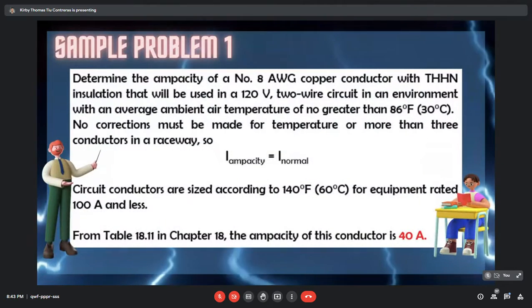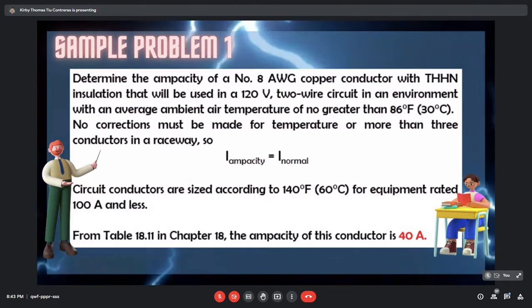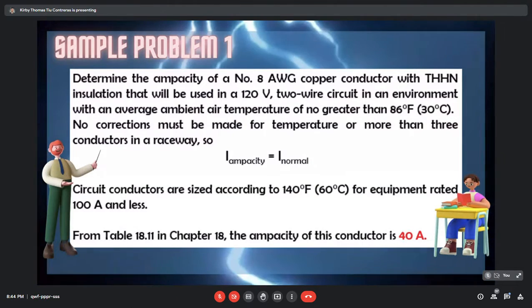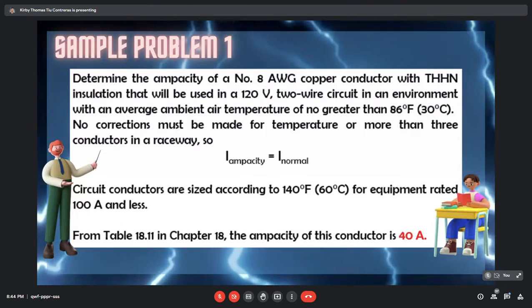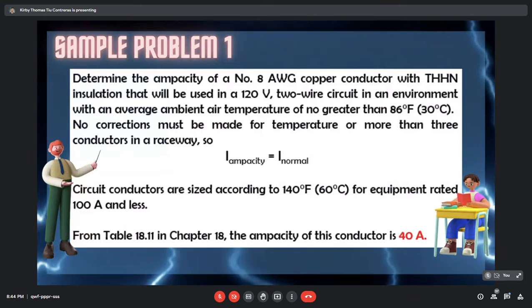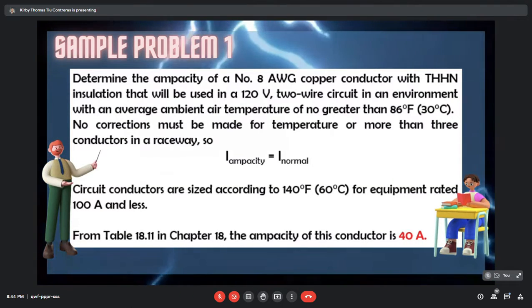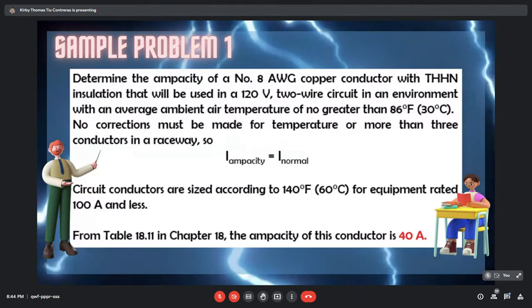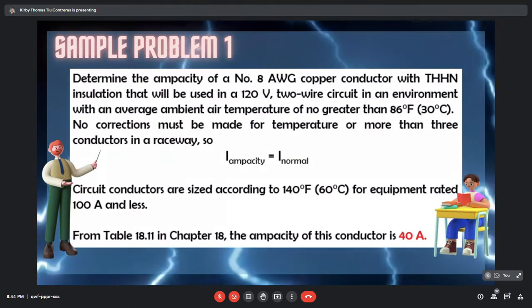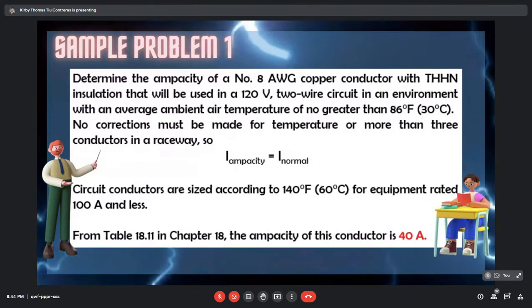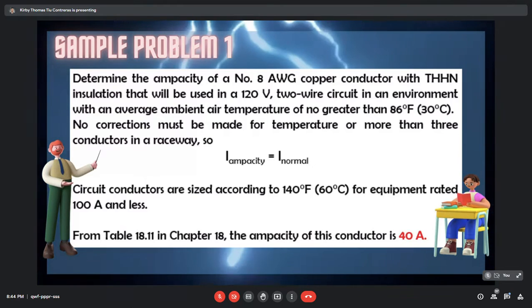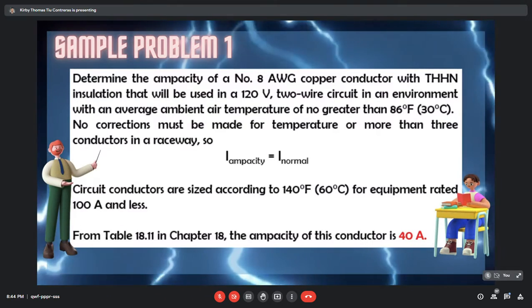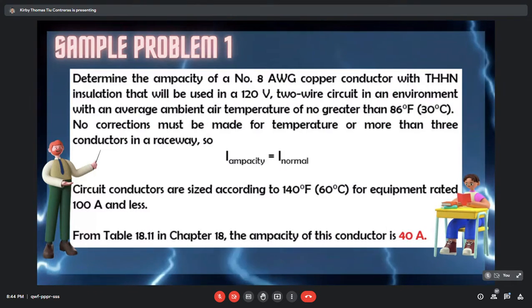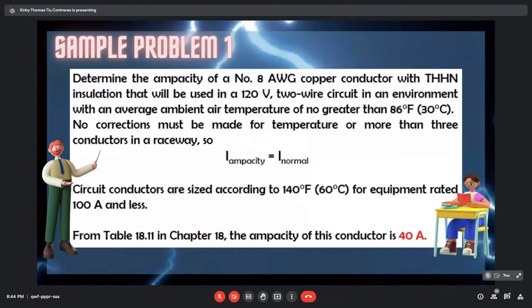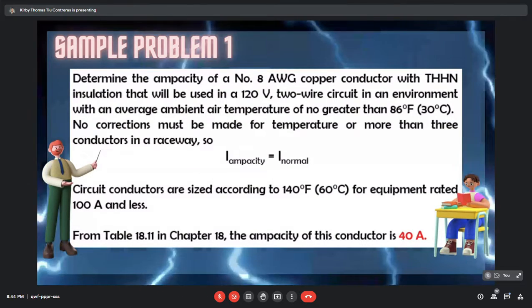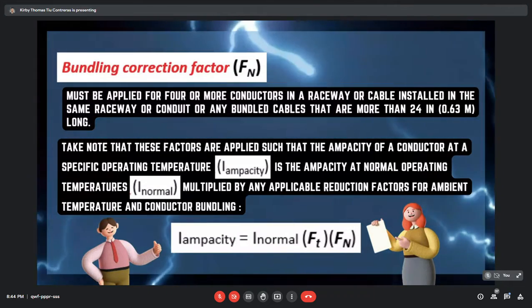So proceeding with the example: determine the ampacity of a number 8 AWG copper conductor with THHN insulation that will be used in a 120 volts two-wire circuit in an environment with an average ambient air temperature of no greater than 86 degrees Fahrenheit or 30 degrees Celsius. No corrections must be made for temperature or for more than 3 conductors in a raceway. So, since it is mentioned na no corrections must be made for temperature or more than 3 conductors in a raceway, we simply mag-assume lang ang ampacity in normal operating temperature niya is equal to the ampacity at the specific operating temperature.